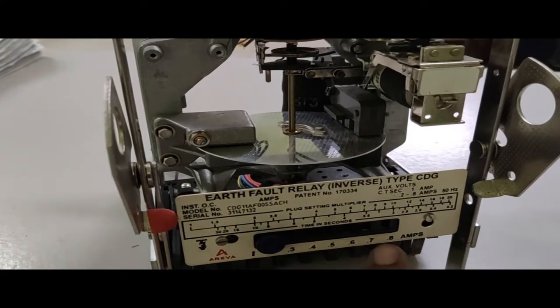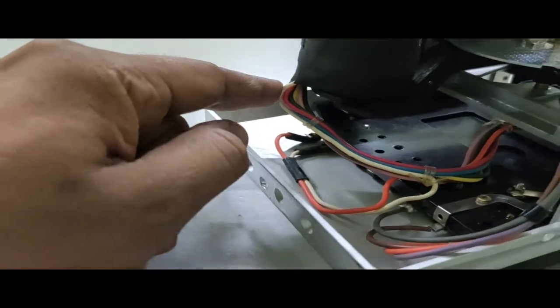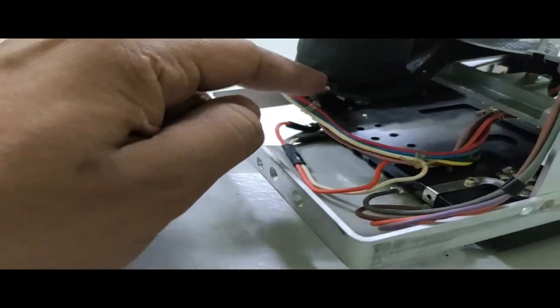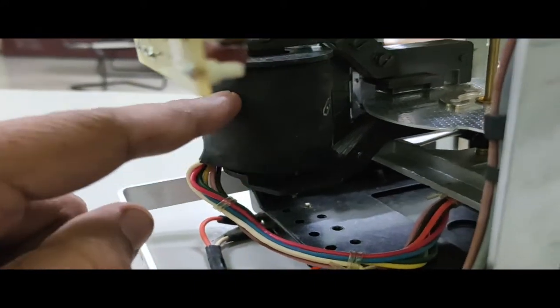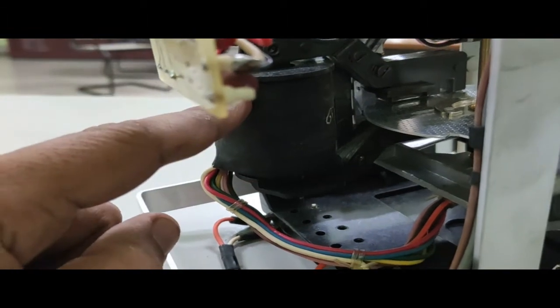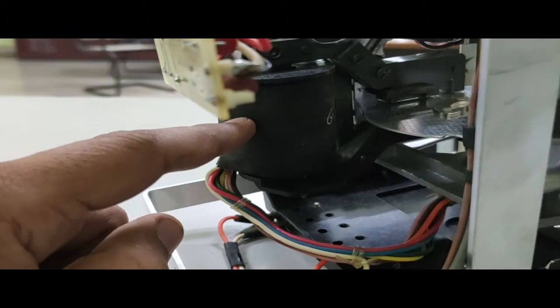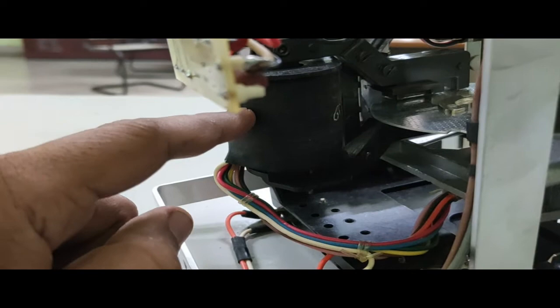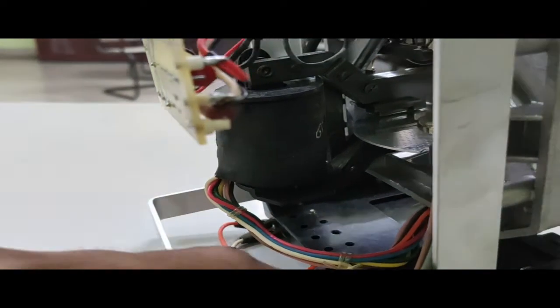The range is 0.2 to 0.8 ampere. So how is this done? This is done through the tappings only. This is the relay coil, and so many tappings are there. Based on the tapping, sometimes the relay is operated at 0.2 ampere, sometimes at 0.8 ampere.